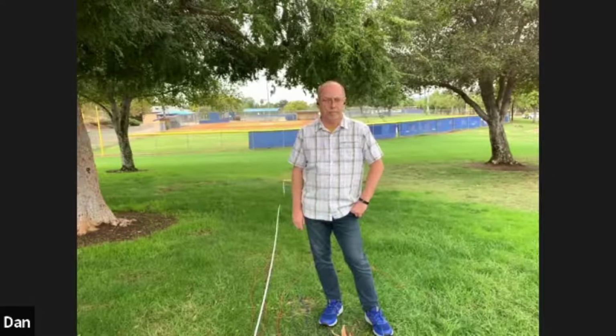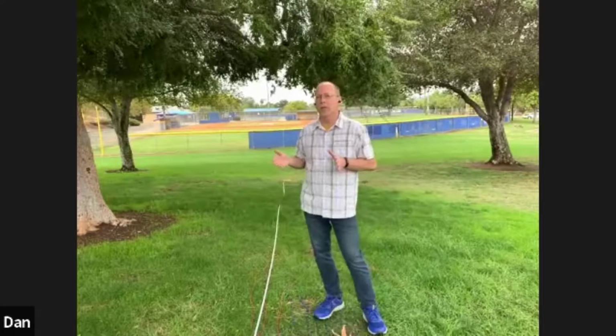It's not as resistive. Right, and that's due to particle size. Fine granule soil, clay and silt, has lots of soil particles to touch that ground rod or probe. Coarse, gravelly, or sandy soils have less contact because there's bigger particles. The other thing is some sandy soils have a lot of silica in them—silica is what glass is, and glass is a wonderful insulator. So generally, sandy and gravelly soils have a harder time getting that low resistance, but it's really easy to drive the rod.